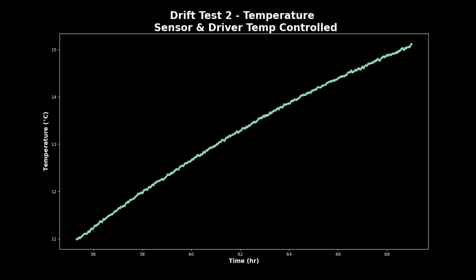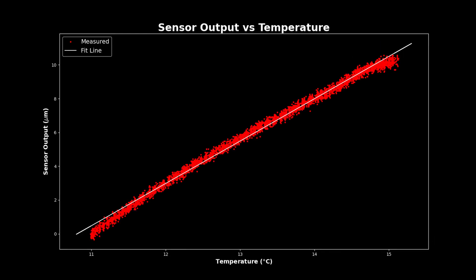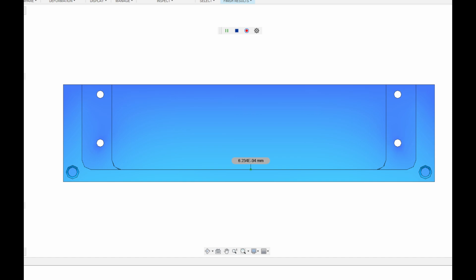Jumping back to the task at hand, let's see how the thermal drift looked when both the sensor and driver are allowed to warm back up. Ah, much better. This time we see a much cleaner correlation between the measured temp and the sensor's output. Applying a linear fit to this data, we can finally get ourselves the thermal sensitivity number we've been looking for. And it came out to right around 2.5 microns per degree C.